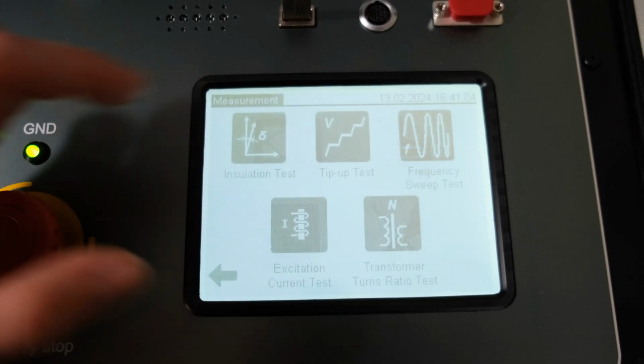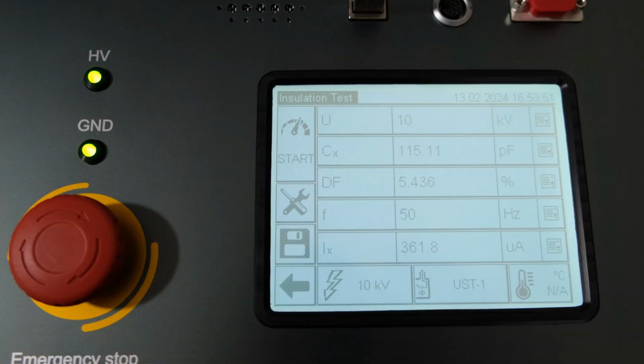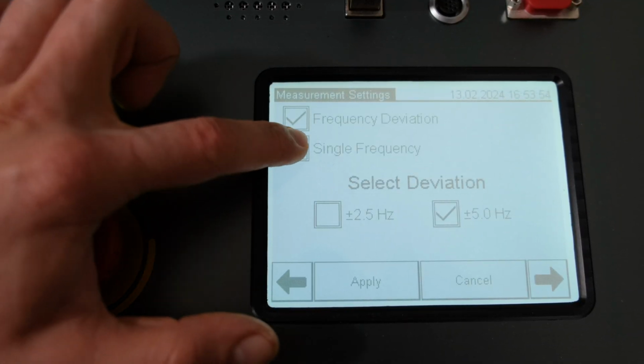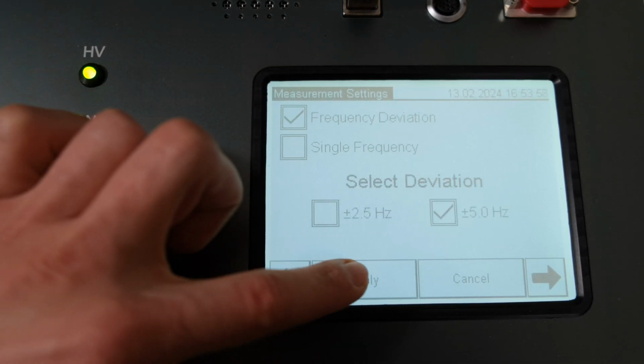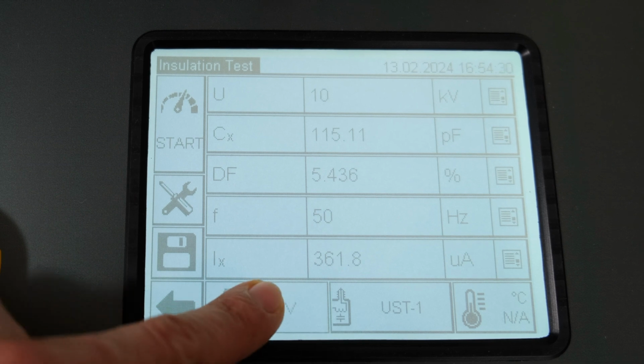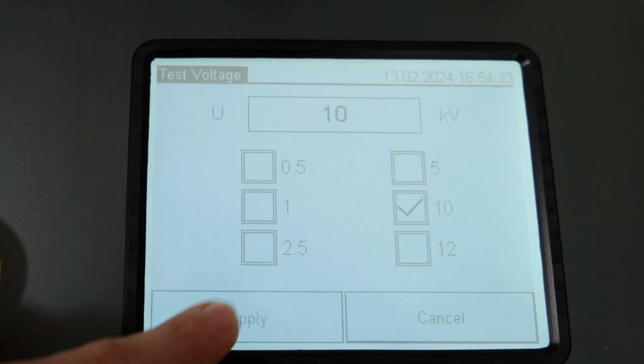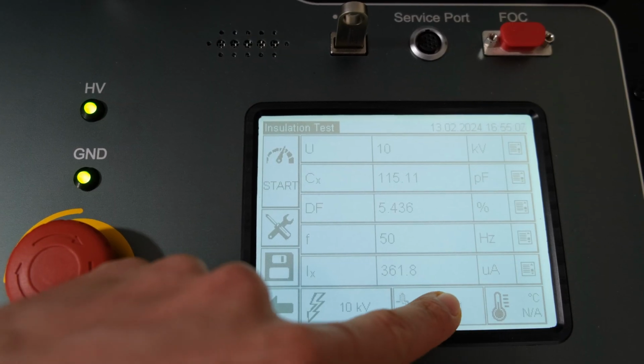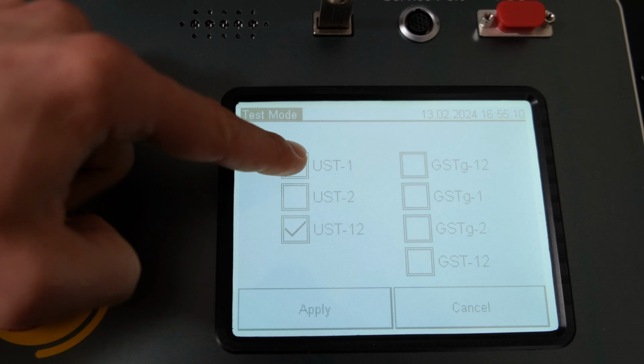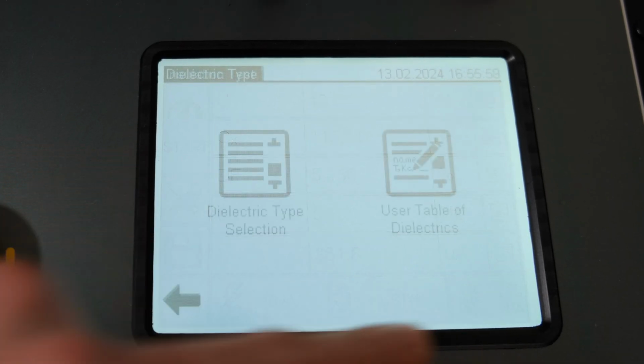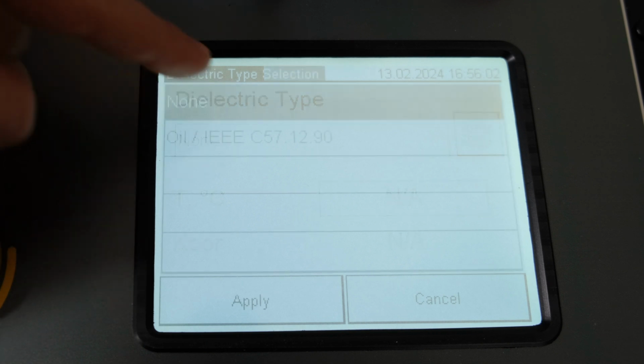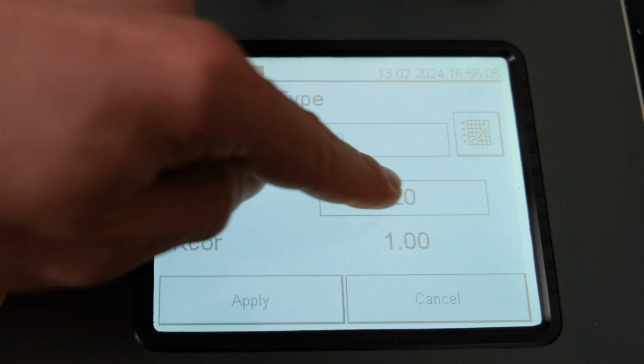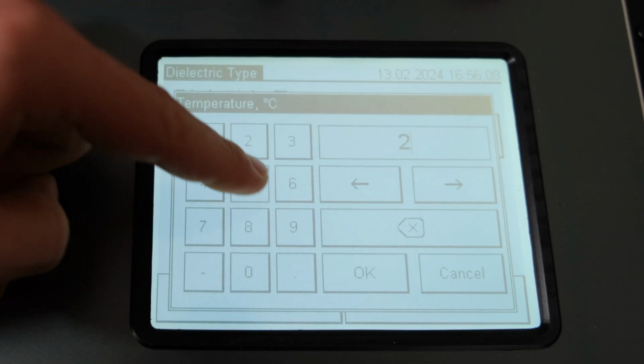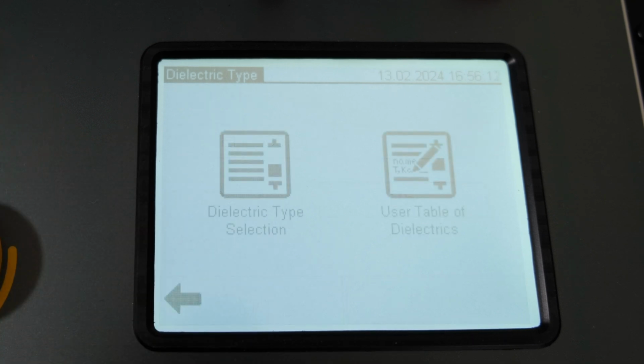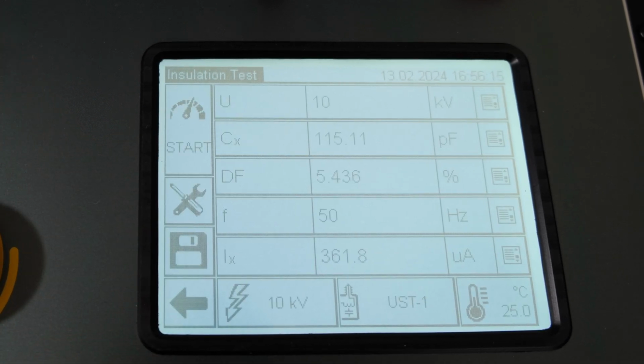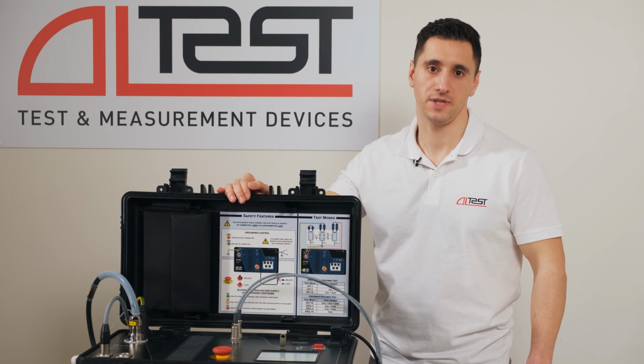In the insulation test mode, it performs measurement settings. Go to Settings and indicate that we're working with frequency deviation to suppress interference current. Select deviation frequency. Select the voltage of the test. Select the test mode. The device performs temperature correction of the measurement results, bringing the measured value to 20 degrees. To do this, enter the temperature dependence of the measured dielectric and specify the current temperature value. By default, one type of dielectric is registered in the device. It is oil. If necessary, you can choose different types of dielectrics.